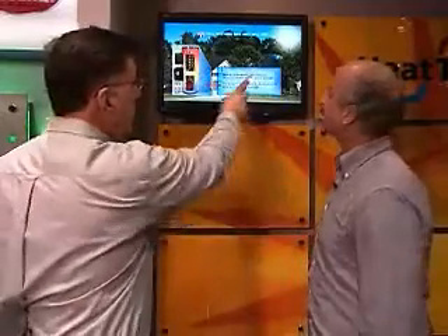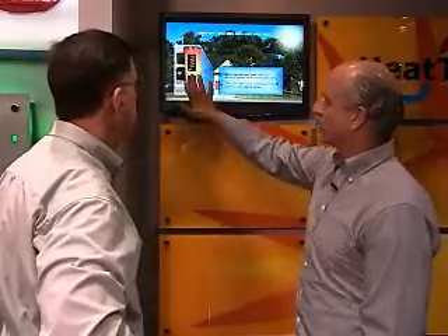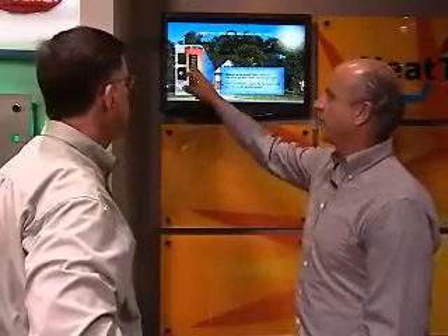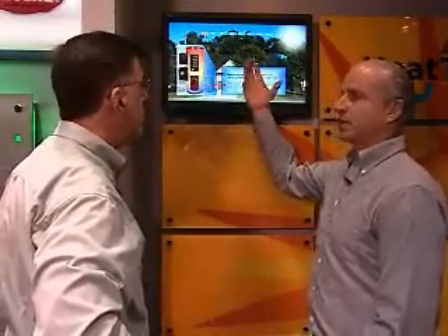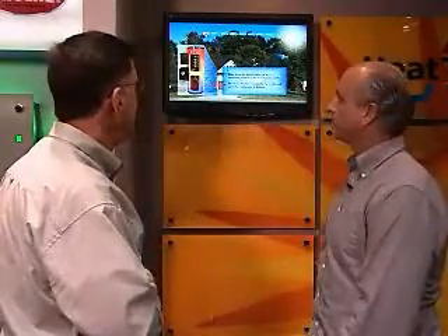Sun's primary. Can I use antifreeze in the panel? Yeah, you can. The one thing they require when you get an SRCC listed product is that you use a Class 1 toxicity glycol, and most of the manufacturers that have certified equipment have that listed, and that's the glycol they recommend. Okay, that's great. So again, you just see how we're driving the heat up, and this backup only comes on if we see a need to satisfy either the space heating or the domestic. It's that simple. Otherwise, the sun does the job. I love the simplicity of it. It's nice. Really nice. Great. Good stuff.